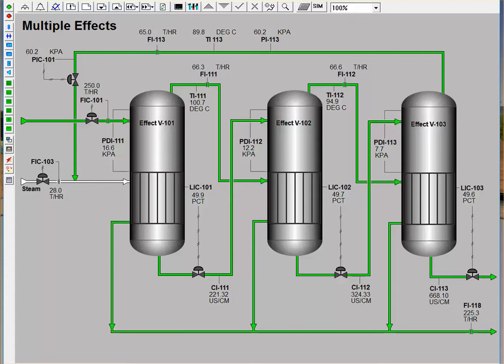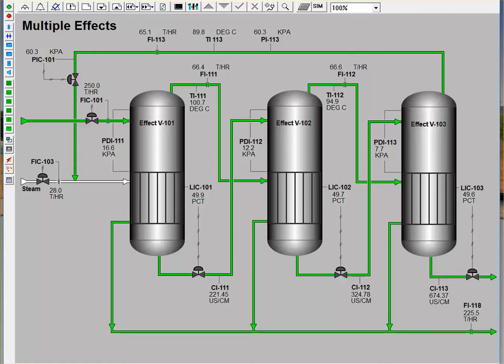To control the brine level in each evaporator, level controllers are utilized to manipulate the flow of brine leaving each evaporator. You can also see that the pressure decreases with succeeding evaporators. The evaporator pressures are kept at specific values in order to ensure two things: one, that the steam entering each effect can evaporate, and two, that there is an appropriate amount of water resulting from the brine mixtures.